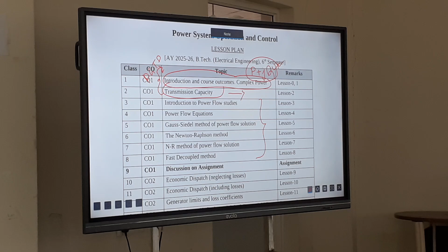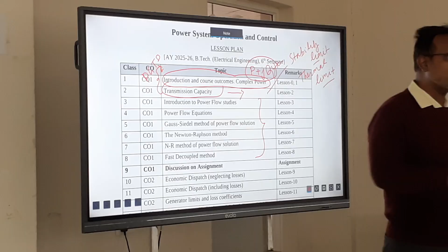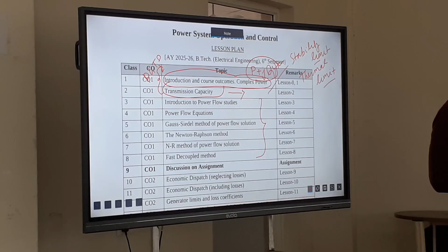One is known as stability limit. The other one is known as the thermal limit. Thermal limit and stability limit. So if you work too hard, you may damage your health irreparably. It may be irreversible. A similar thing is the thermal limit for a transmission line. So what does thermal limit mean? Thermal limit means whenever power transfer occurs, I square R losses occur in the transmission line.